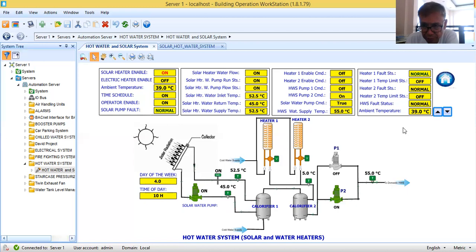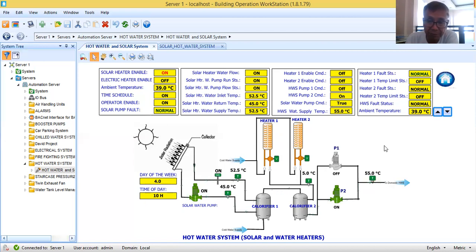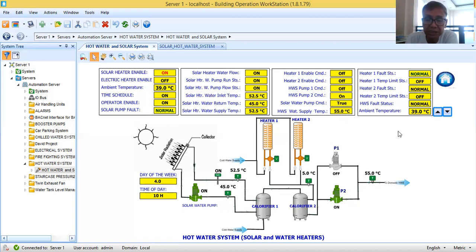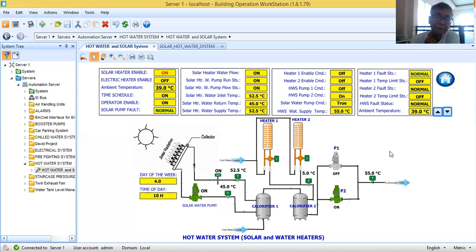I asked the engineer in charge to provide the control and monitoring points from their system so we could do software integration. For those new engineers, software integration means that to get information from their system controlling the hot water, I run one communication cable from their system and connect it to my BMS system. We can get the information through BACnet over IP or BACnet MSTP.